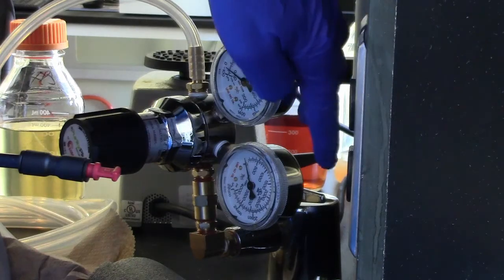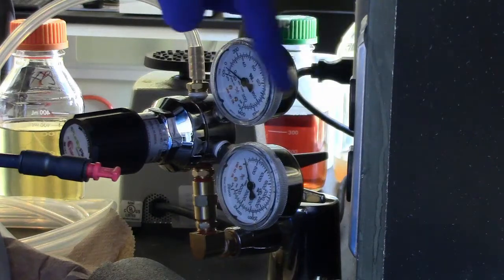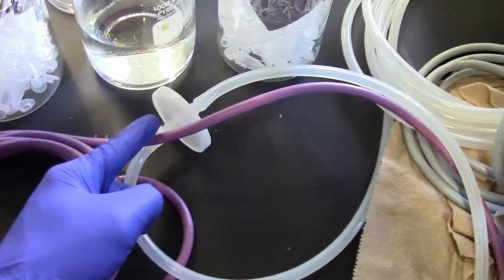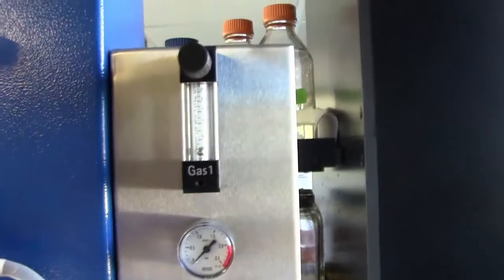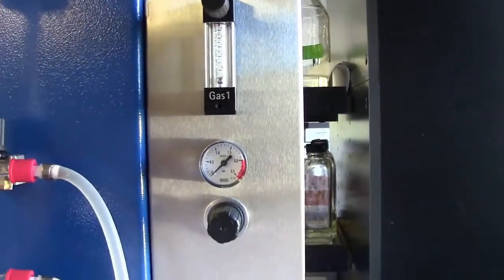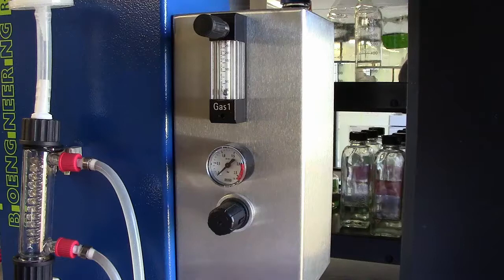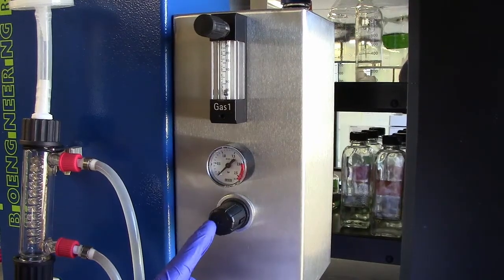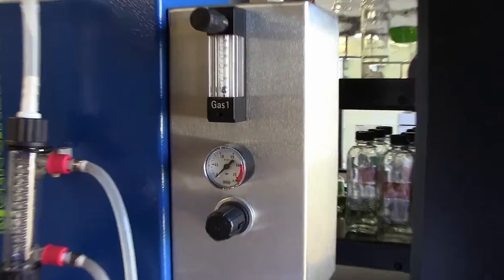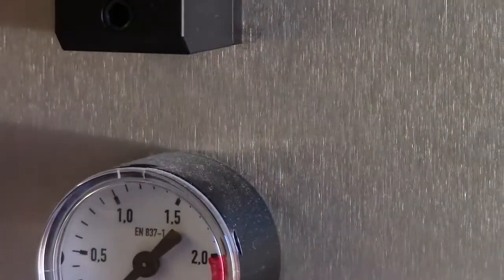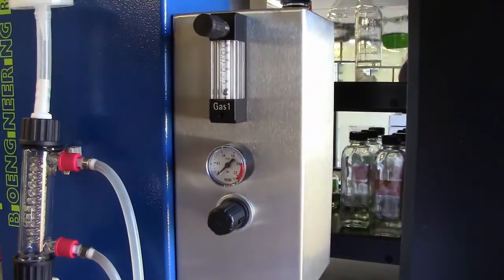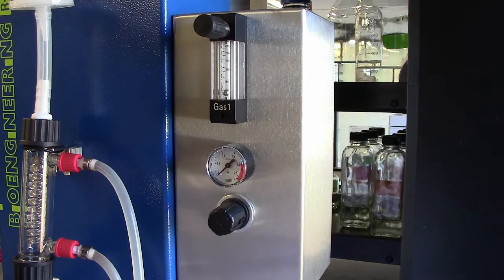There are 2 gauges on the regulator, one for the inlet and one for the outlet. The outlet air flows from the regulator through a sterilization filter, then enters the side of the control tower and is channeled to the gas module on the top right of the machine. The gas module steps the pressure down further to provide gentle aeration in the culture media. The bottom knob on the module is the pressure adjustment valve, which is another step-down regulator. Since our air supply is already controlled by the regulator attached to the benchtop air supply, this valve can generally be left in a fully open position.